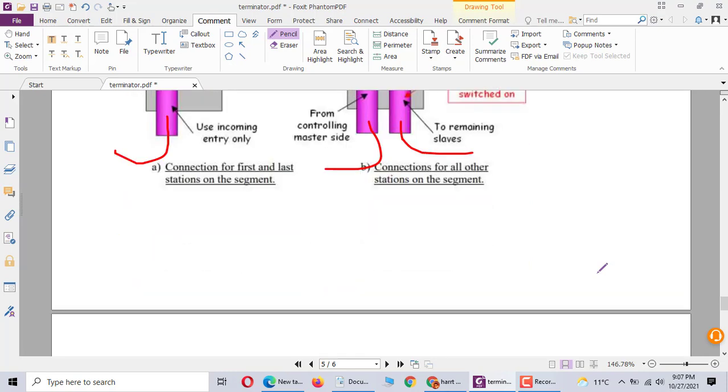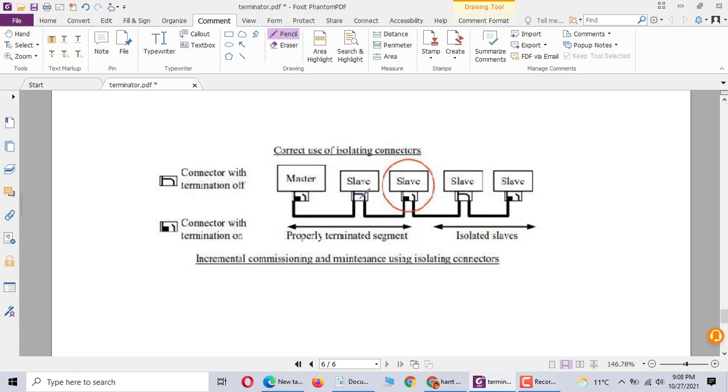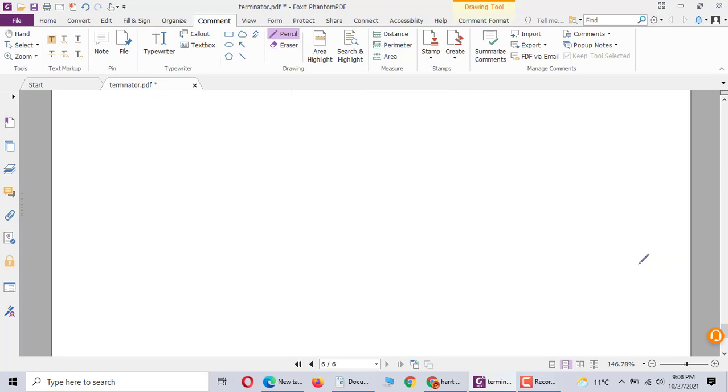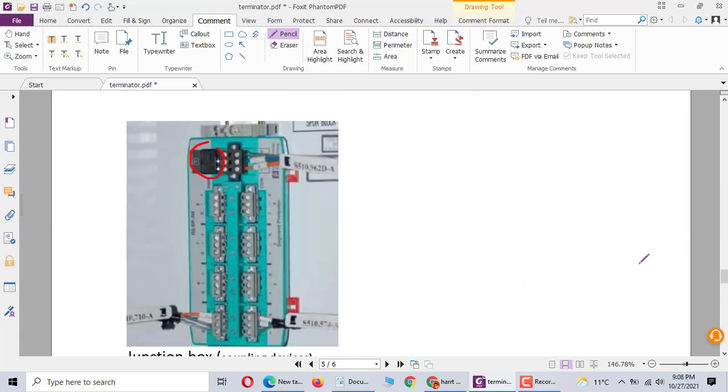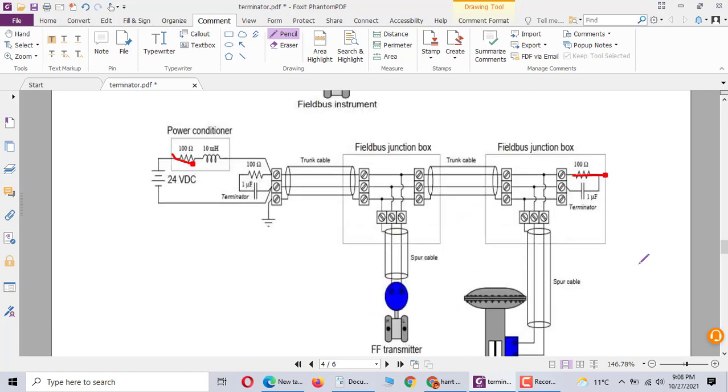Profibus DP master termination is on, the termination resistor is on. In the middle, this one and this one don't work, so you have step one, step two, step three, the termination is off. Last one slave, the termination should be on. That's it, this is the communication terminal resistor. Thank you very much.